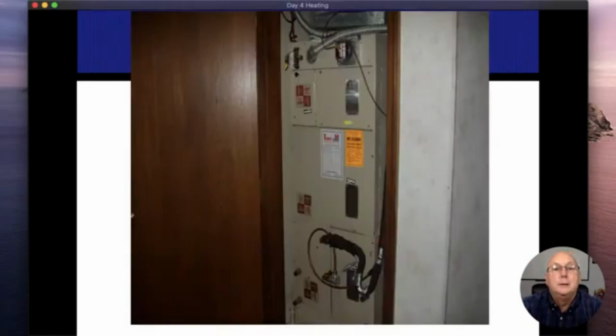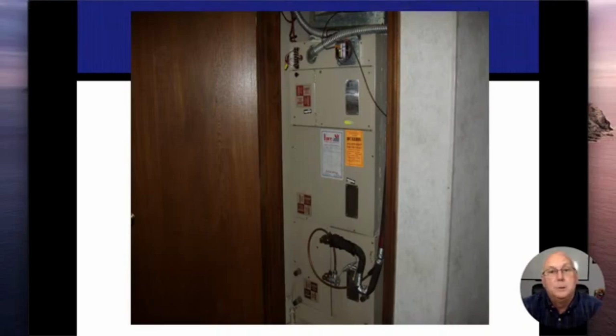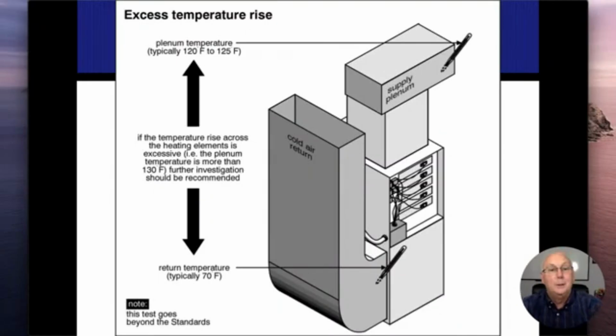All right. This is what one looks like. Me personally, it's a 240 volt appliance that I just would not touch. All right. It's going to be easy to get one of those cover plates and touch one of the heating elements, short the whole thing out. You're going to create one hell of a problem. So really the only thing we're going to want to do is turn it on and check for a temperature rise. I got nothing else here that I can give you advice on for it as well. So just do your temperature rise and that's about it.